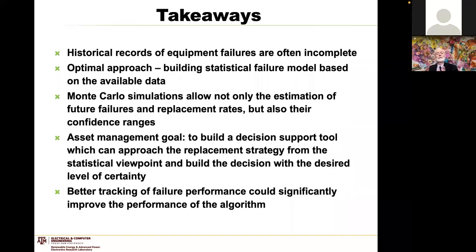So the takeaways of this process, which I understand was described quickly and perhaps isn't conducive to thorough understanding, is that we deal with historical records of equipment failures, which don't include information about breakdowns or exposures to extreme fields, moisture, and extreme weather. Using a statistical failure model based on the available data, we perform Monte Carlo simulations with that model, identify the characteristics of the relevant functions, and then estimate the effect of replacement rates, assuming new replaced devices will operate with very few failures for a while and only begin developing failures after prolonged exposure.